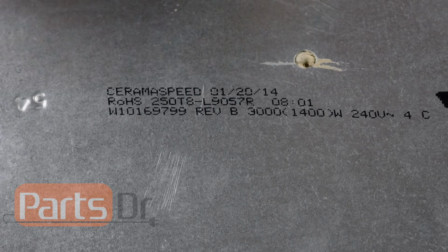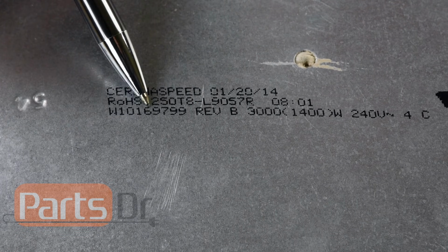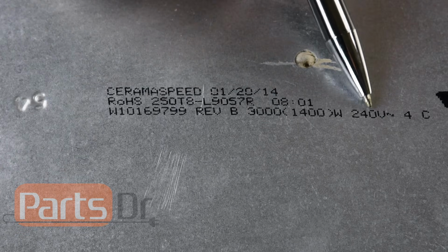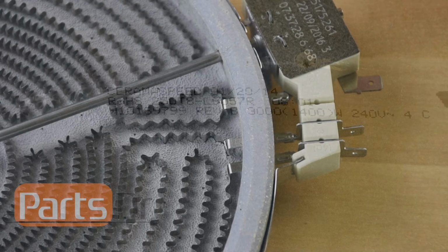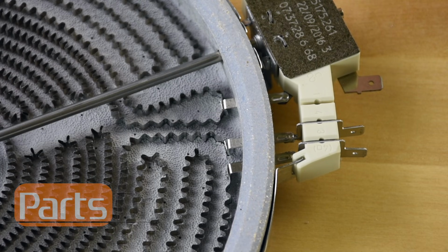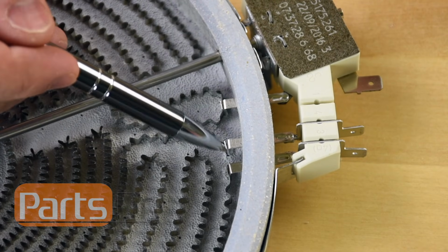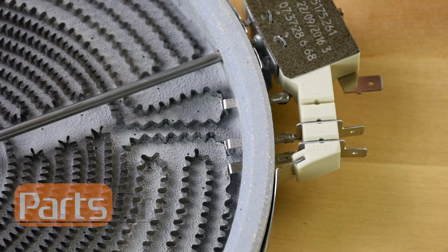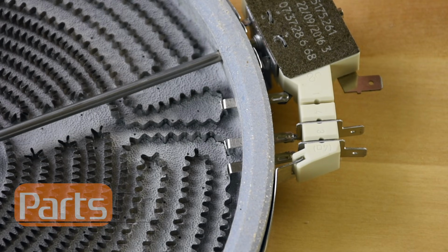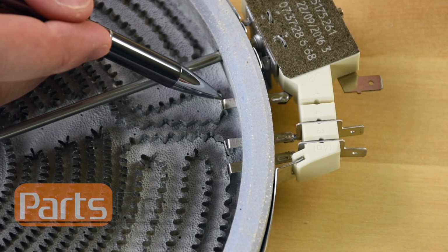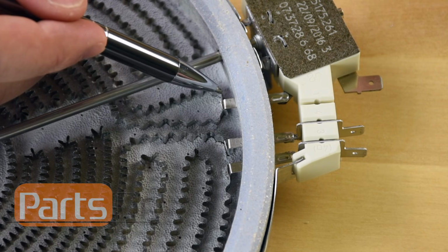If you look at the back side of the element, the manufacturer will often print the part number, wattage ratings, and voltage rating on the back side of the element. There are single, dual, and triple coil elements. To determine how many coils your element has, you can look at how many electrical connections come out the side of the element. A single element will have 2 connections, a dual element will have 3 connections, like this one, and a triple element will have 4 connections. On dual and triple elements, you will notice one of the electrical connections has multiple coils that tie into the same terminal. This terminal is called the common terminal. Please make note of this terminal for testing the element.